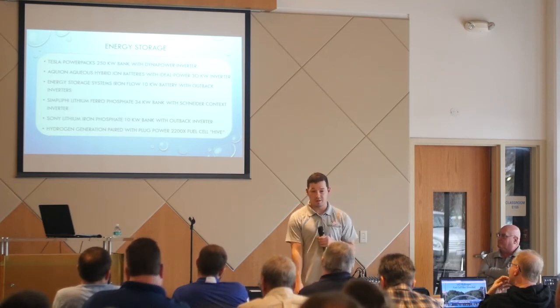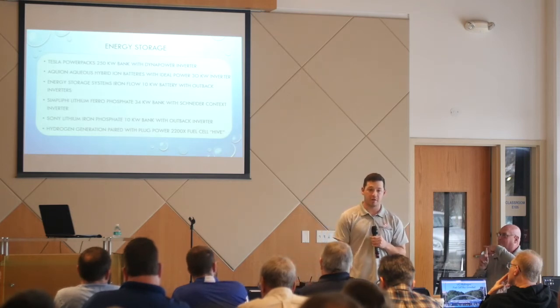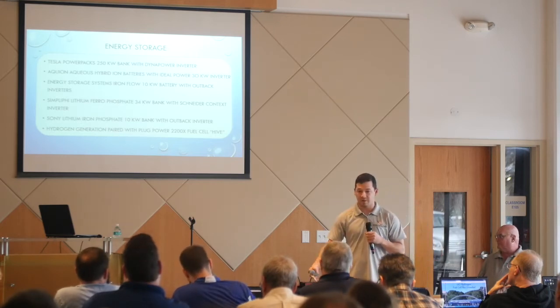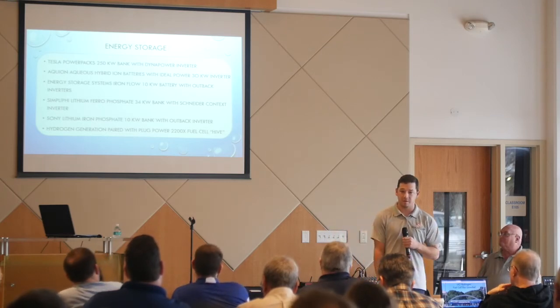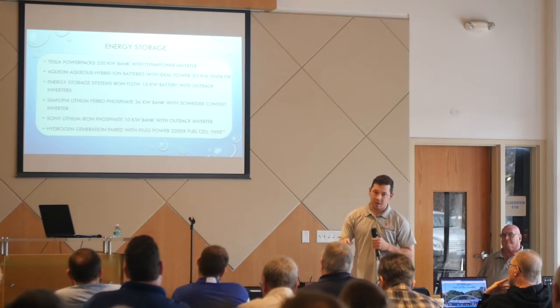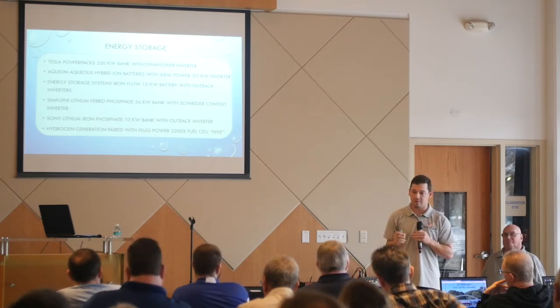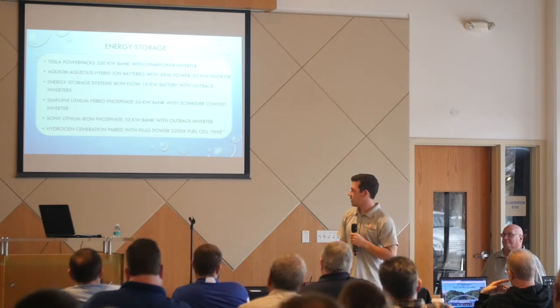So communications is another big critical junction in a microgrid, because if you lose communication, you lose the ability to make decisions, and you have to be able to send set points, turn things on and off, even when the macrogrid fails. So that's what we call our critical grid. So we have our microgrid trunk line, which is running around 480 volt 3-phase, and then we have our critical grid lines that are just spurs off of that, all 120 single phase for critical systems.